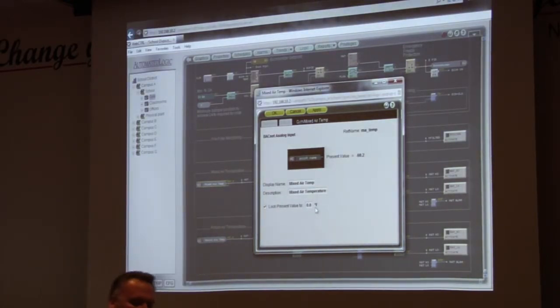Okay, and I'm going to say, fine, I want to lock it to 55. All right, okay, so I'm going to lock this temperature at 55.123. Doesn't matter. Did you notice when I put the 1, 2, 3 and it still kind of shortened it up? It says I'm only going 1. So lock your chill water supply temperature at 55. I got the check there.